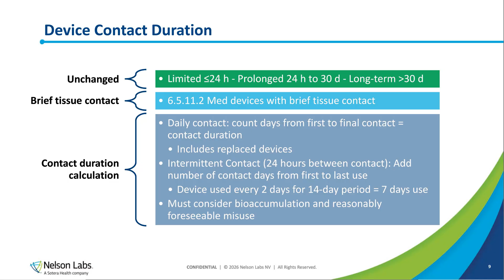We have also a new concept, which is the intermittent contact, and that's a contact for which we have 24 hours between each contact. In that situation, you add the number of contact days from first to last use. So if I use an example, if a device is used every 2 days for a 14-day period, that's a total period of use of 7 days. And as I mentioned previously, the concepts of bioaccumulation and reasonably foreseeable misuse also need to be considered in your device contact duration.